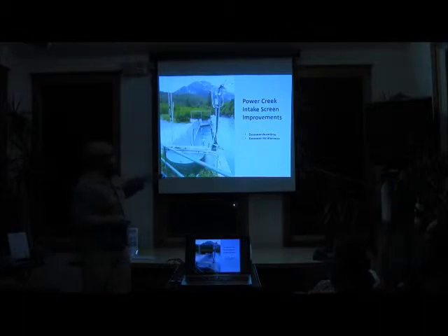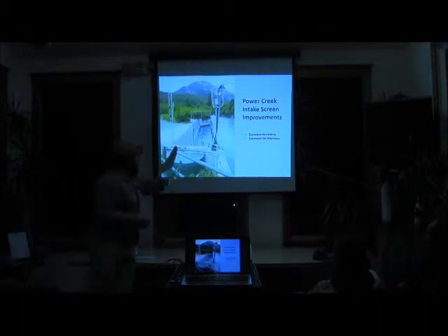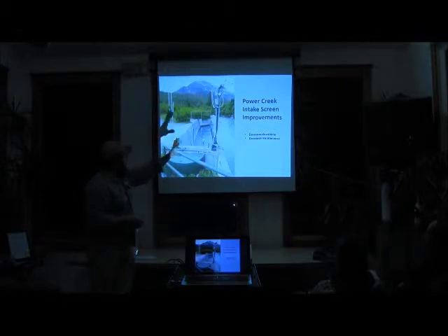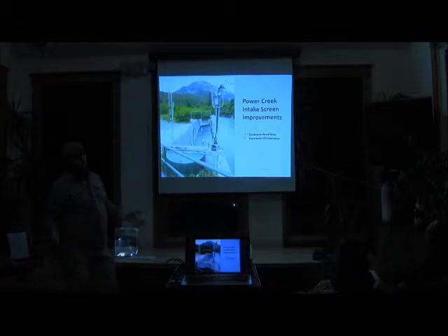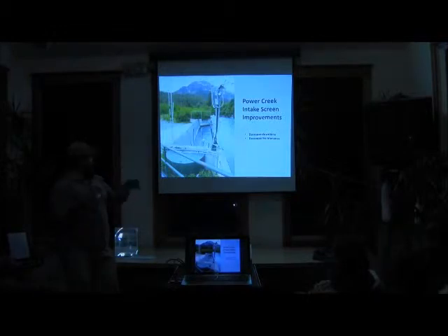Otherwise they get clogged. And you can see those little posts sticking out of the water. Right in front of that is where the creek bed is, and because of that eddy effect, gravel builds up there. Especially when we have big storms, like a couple weeks ago, we have to dump the dam. You'd think with a lot of rain you could be 100% hydro, but when we get those big storms, we're actually probably running a diesel generator, because the gravel builds up and it clogs.